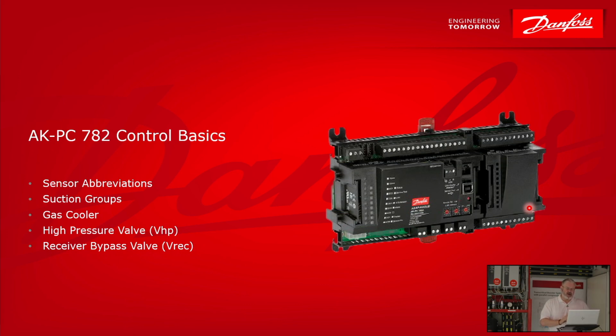So our controller, our product line that we use for commercial refrigeration, this AK, it's on the front of every part number we have. It stands for ADAP-KOOL. That's the name of our product line. And then you have the hyphen, and then PC stands for pack controller. Some of our other products, the AKCM, that's a communication module. AKXM, that's an expansion module. So this kind of follows that. And we call this wonderful and amazing controller you can see on your screens now the PC782 pack controller. I want to just briefly touch on how we use that to control a transcritical system. So we're going to look at the sensor abbreviations that are confusing for some, and then we'll touch on the main control areas.